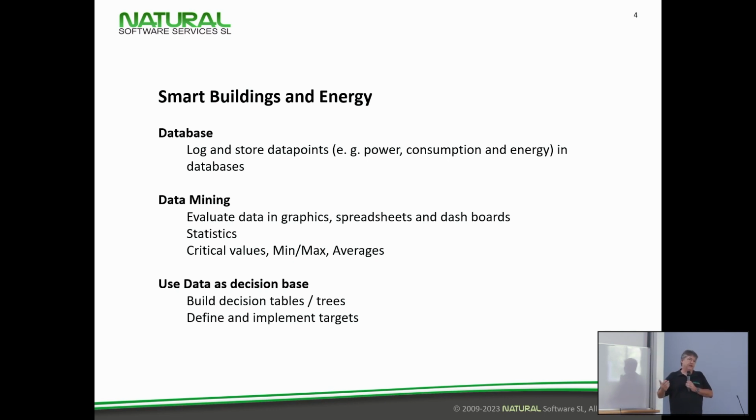Up until about 2 years ago, we just had simple logic modules in there. For example, if the humidity gets too high in a room, we start the ventilation, or we start the fan coils in dry mode, or send off an email that something is going on in a building that you have to look at for the humidity. Perhaps you're going to get mold or something.